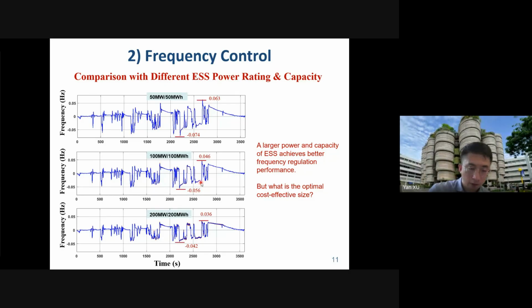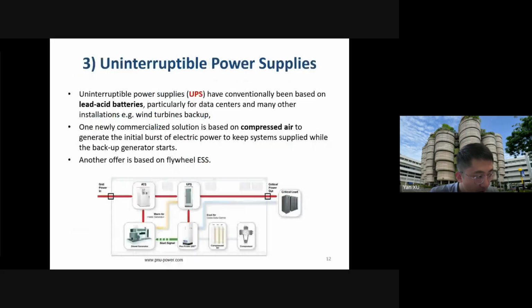Practically, we can go through different sizes of the ESS and simulate the corresponding frequency performance, finding a balance between the two. We calculate the total capacity divided by the total performance index to get a sensitivity value. The optimal size is the one with the marginal sensitivity value, meaning that further increasing the ESS gives only marginal improvement in frequency performance. That's the basic idea for optimizing the energy storage system size.